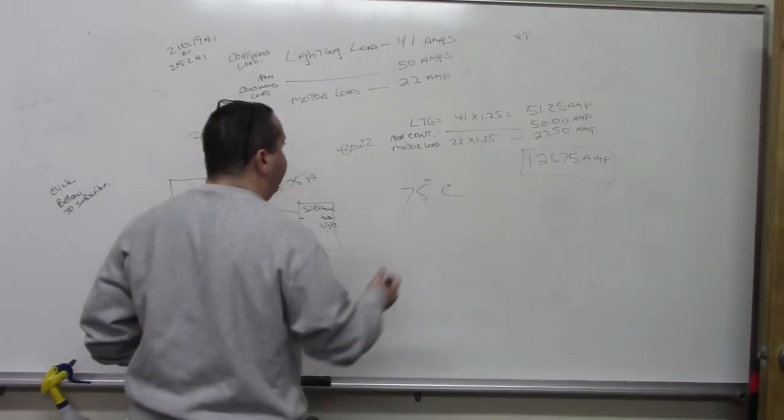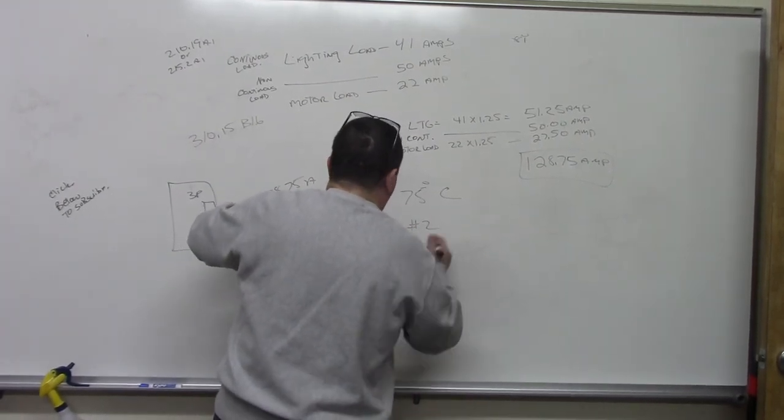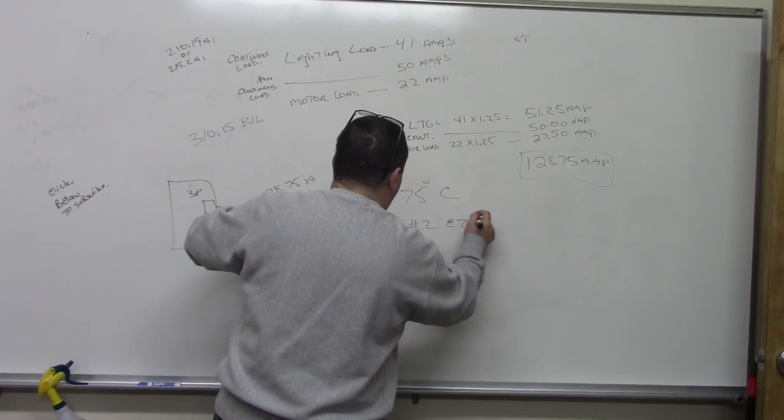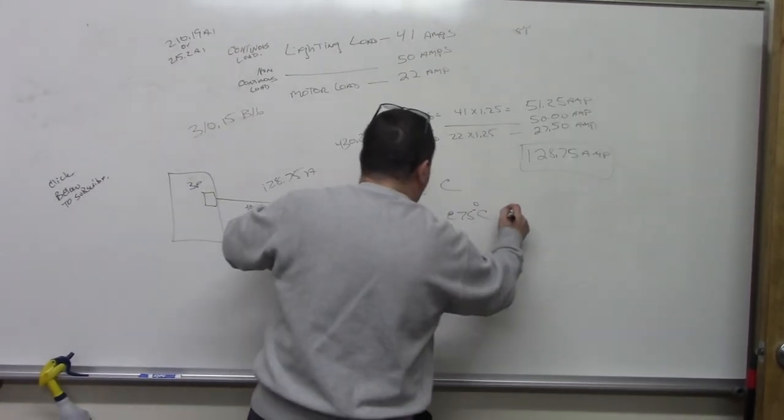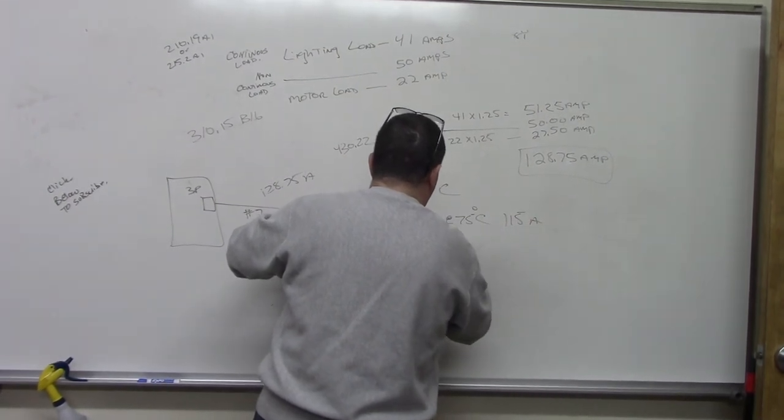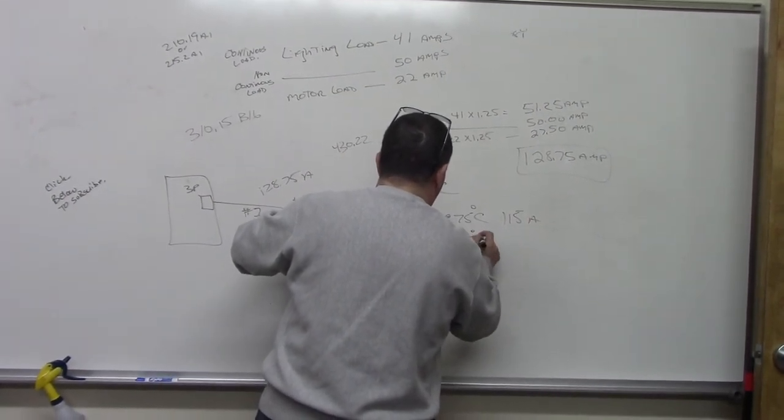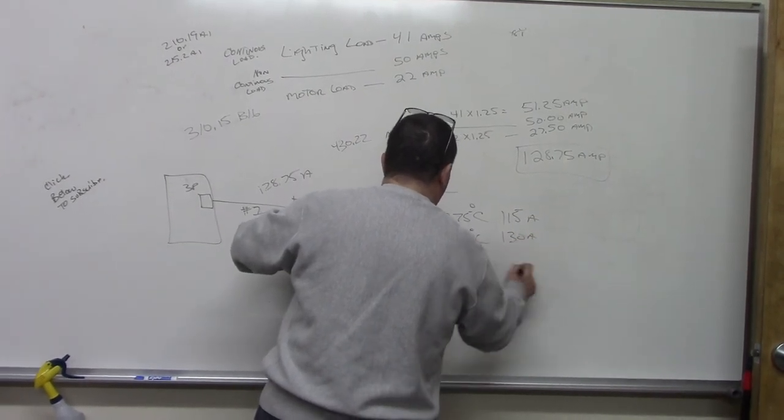We've got to go to the 75-degree column. Let's see. There's no derating here. No nothing. So a number 2 again at 75 degrees. I apologize. It's 115 amps. And the number 1 at 75 degrees Celsius is 130 amps. So we're going to use this.